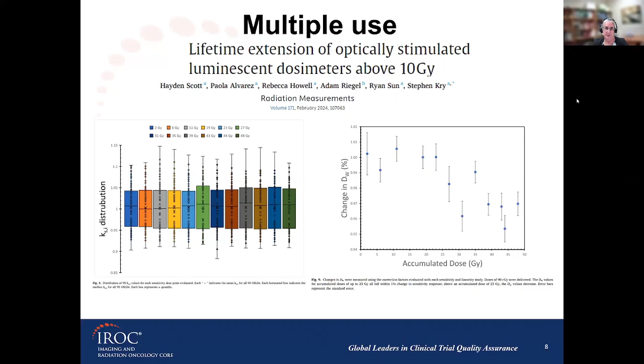The second parameter is the performance of the system. Task Group 191 suggests that you can reuse them without any change in the performance up to 10 gray. Vendors suggest not to reuse, but in this case, Scott looked into the performance and was able to find consistency up to 23 gray accumulated dose. So this gives the room to actually reuse the system in a safe way.